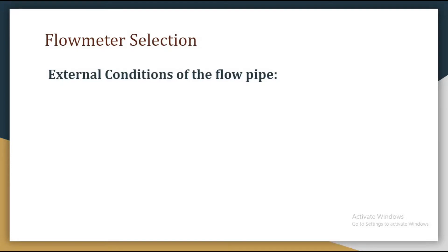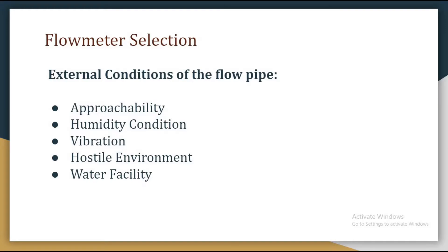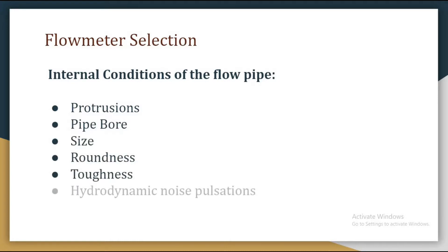The next thing is external conditions of the flow pipe. The first is approachability — it is important to know whether, once the meter is installed, it is accessible for removal or recalibration. We also need to be familiar with humidity conditions, vibration, hostile environment, water facility, etc. Internal conditions of the flow pipe include protrusions, pipe bore size, roundness, roughness, hydrodynamic noise, and pulsations.